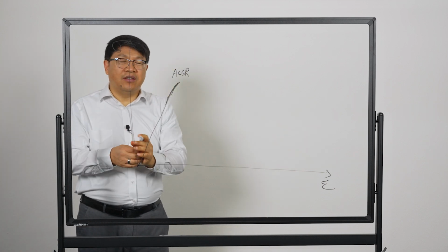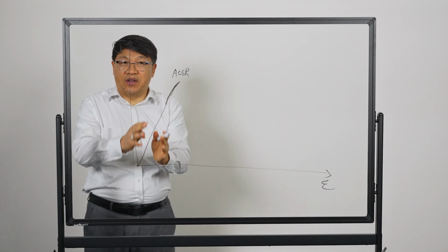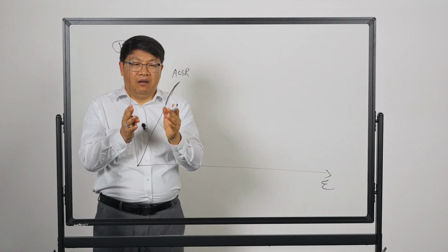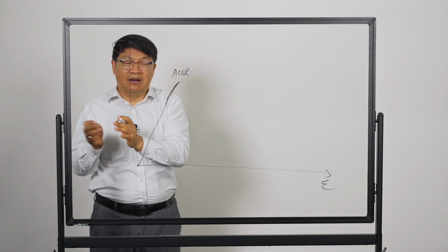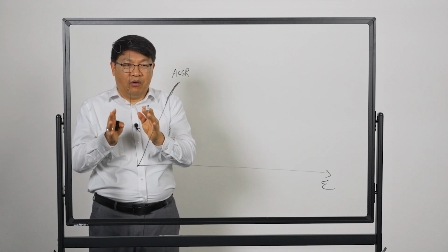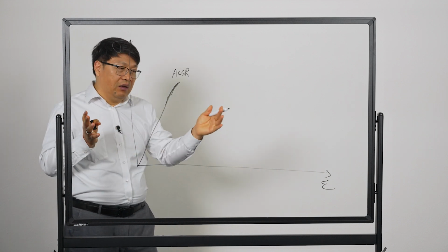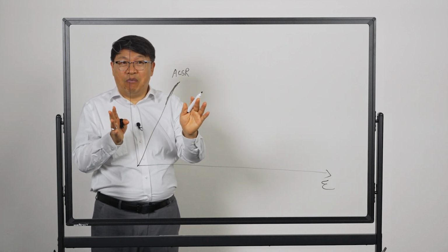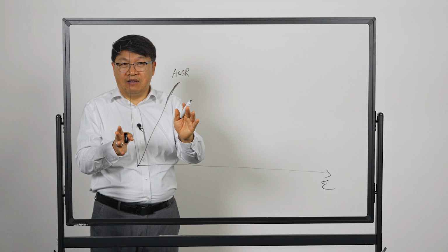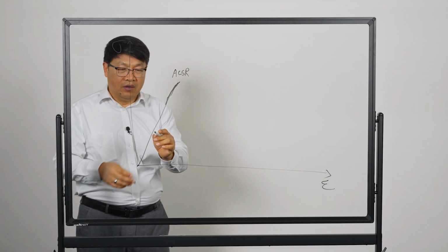You can use what is called linear approximation in stress strain. Quite a few countries still use that in their sag-tension design. What needs to be kept in mind is that when you are working with some of the newer advanced conductors, the stress strain behavior is actually very different, okay? And this is where we have to be careful.